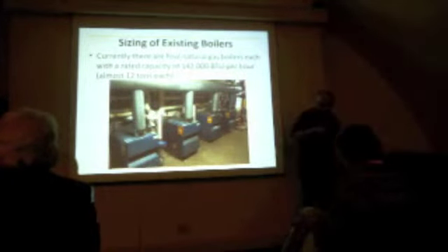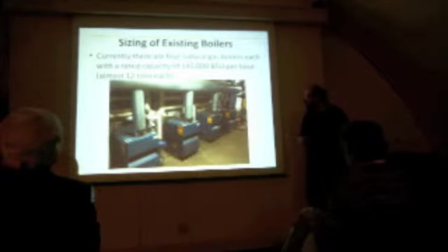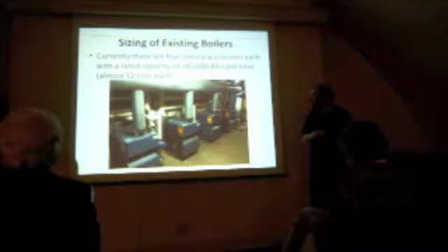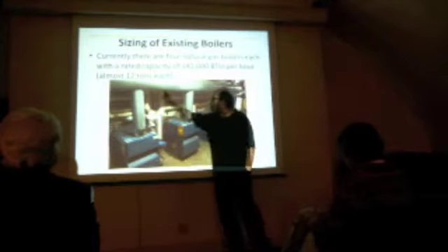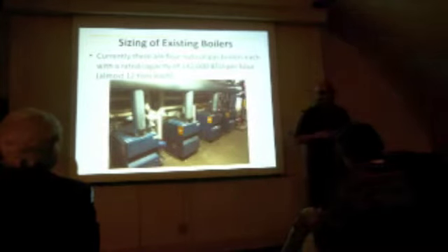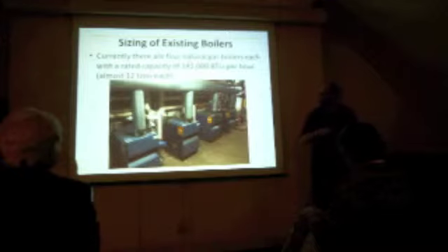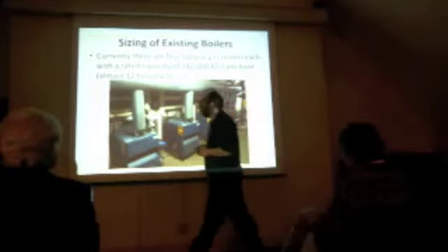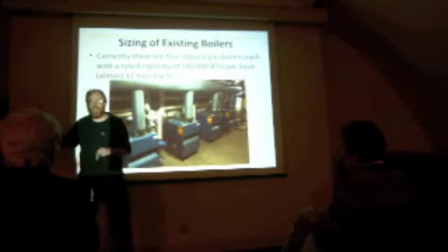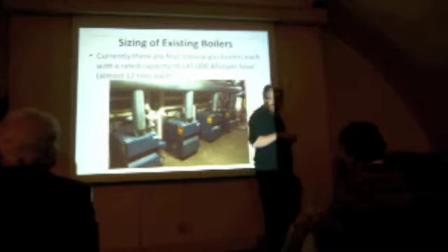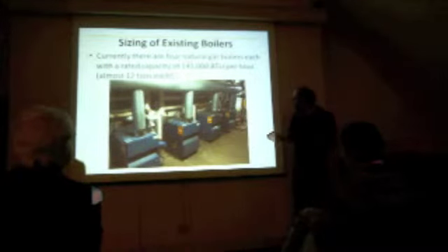So that's the distribution side. On your supply side, there are two different systems for the two buildings. I chose to focus on the one that connects to the sanctuary, this part of the building, and into the office space. It's heated by these four units here. They're all connected basically in series. And interestingly enough, we just found that they ran the exhaust pipe right through the old chimney stack. And that's why this wall right here is noticeably warmer than the rest of the space. That's where that exhaust heat goes out of these pieces. These four boiler units we're going to look at in some detail.